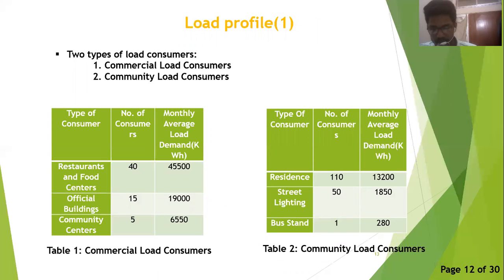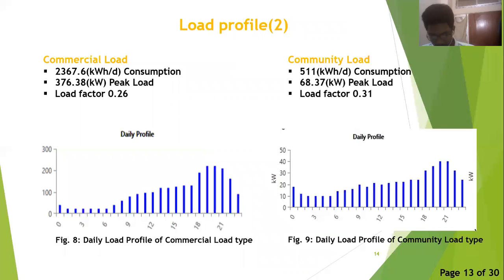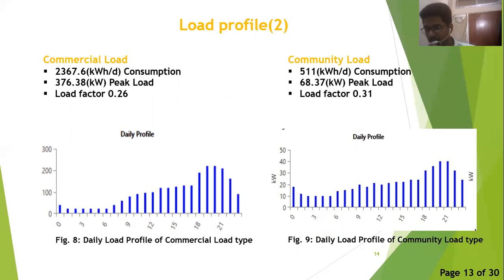About the load profile of the system: in our proposed system, two types of load consumers are defined — commercial load consumers and community load consumers. Their subsequent monthly average load demand are given in tables 1 and 2. The daily load profile of commercial and community type loads are given in figures 8 and 9. The commercial load has a 2,367 kWh/day consumption with a peak load demand of 376 kW. The community load has a 511 kWh/day consumption with a peak load of 68.37 kW.